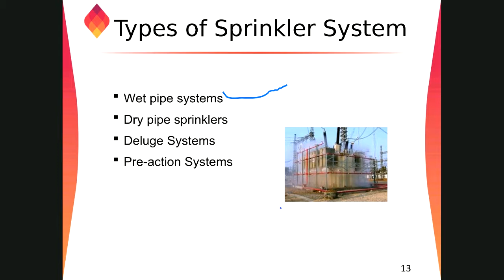So the wet sprinkler system is the most common one worldwide. If you look at this wet sprinkler system in the image here, the number of accessories and fittings is very small compared to the dry, deluge, and pre-action systems. So the more you go to the dry side and deluge side, the more accessories we get, which is very costly and takes lots of effort.